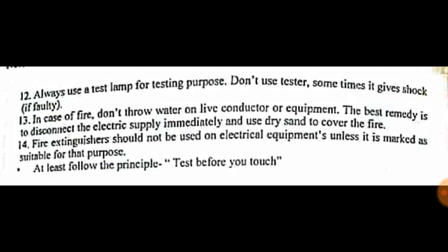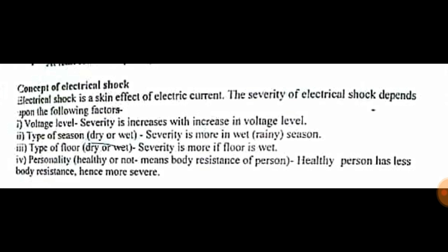Rule thirteen: in case of fire, do not throw water on a live conductor or equipment. The best first remedy is to disconnect the electrical supply immediately and use dry sand to cover the fire. Water-based fire extinguishers should not be used on electrical equipment unless marked as suitable for that purpose. The last rule: always follow the principle — test before touch.